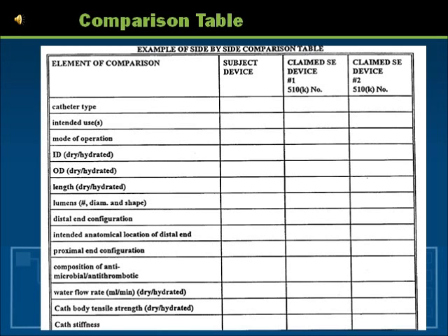A table should be part of this section and address similarities and differences in the following areas, if applicable: intended use, indications for use, target population, anatomical sites, where used, such as hospital, home, ambulance, etc., energy used and/or delivered, human factors, design, performance, standards met, materials, biocompatibility, compatibility with the environment and other devices, sterility, electrical safety, mechanical safety, chemical safety, thermal safety, and radiation safety.